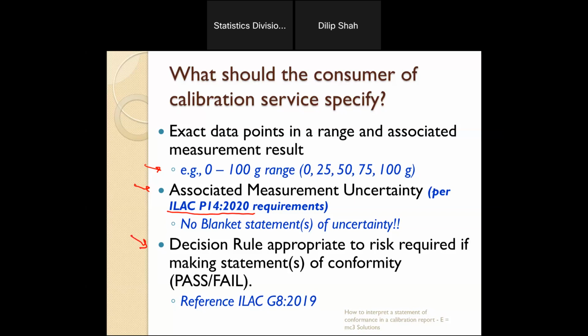But if I take the pressure of the tire of a commercial aircraft, or a fighter jet landing on an aircraft carrier, which has a very short runway, then I want to take much less risk and make sure that gauge is calibrated with a better standard, with a lot less uncertainty in that respect. So those are the kind of things you should watch out for as a consumer of calibration services.